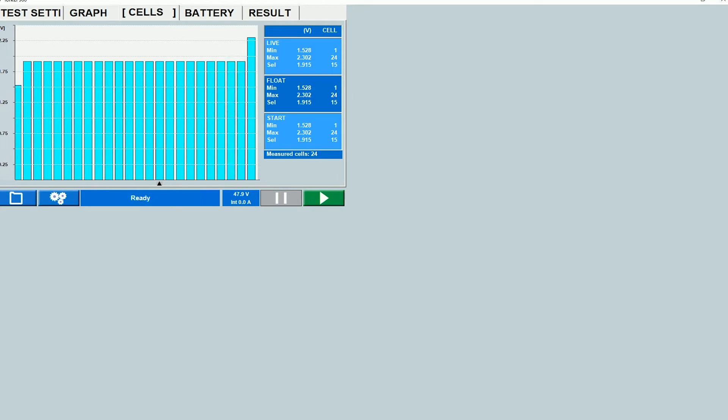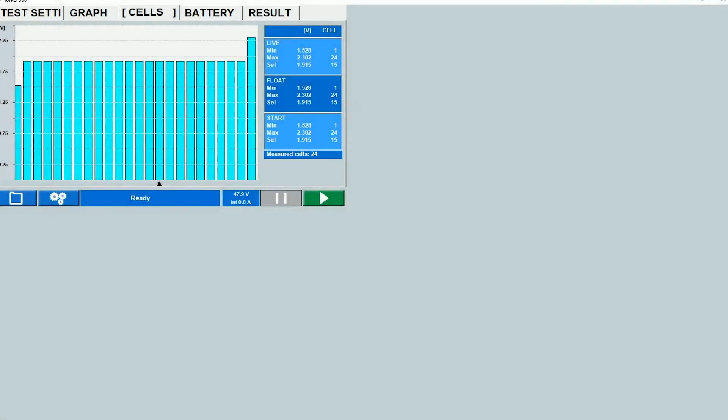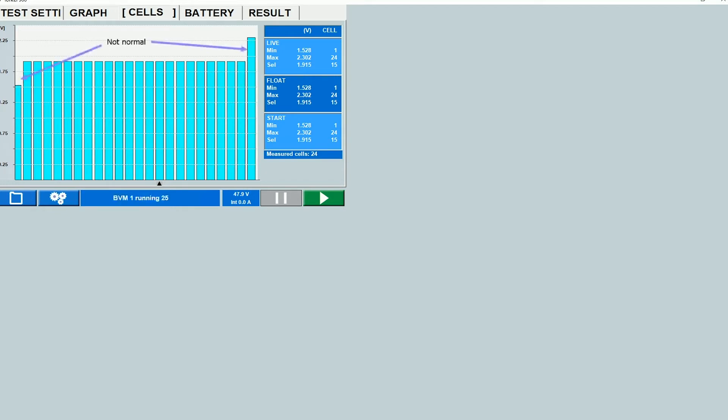You can verify the number of cells over here as well as the number of BVMs over here. The number of BVMs is obviously one more than the total number of cells on the string and you want to make sure that the bar graphs are the same height. When you do a real test you will see that the bars are all at the same height, pretty much the same height at least.